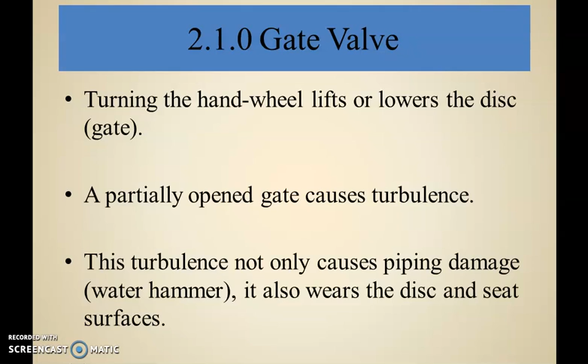These are the various diagrams of the gate valve. Here we can see the seat of this gate valve. When you rotate the wheel, the stem of this gate valve moves in the clockwise or anti-clockwise direction. It moves upward and water starts flowing through this valve. If you keep it half open, using this gate valve for controlling purposes, the pressure of the liquid coming through it may bend this stem. If it bends, it will not fit here properly. So we are not using this valve for controlling purposes. This is only used for on-off purposes.